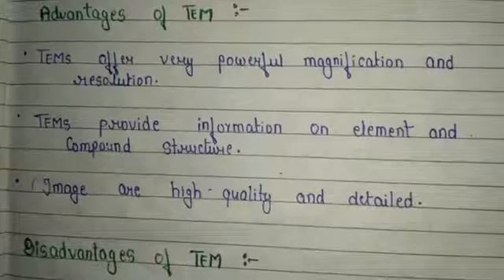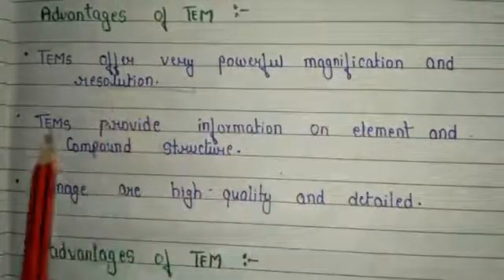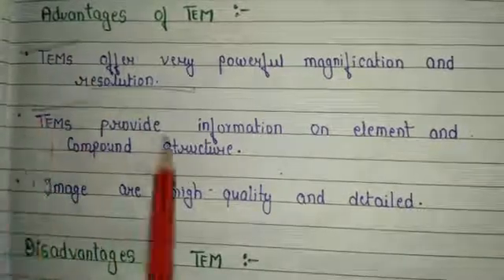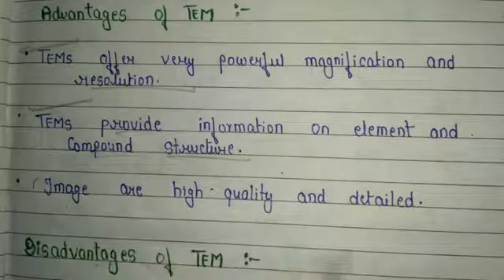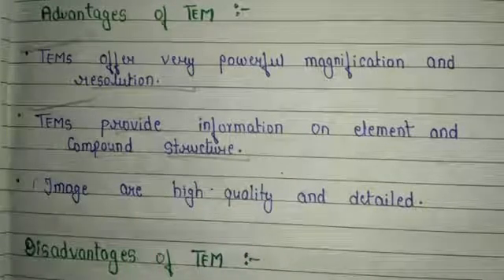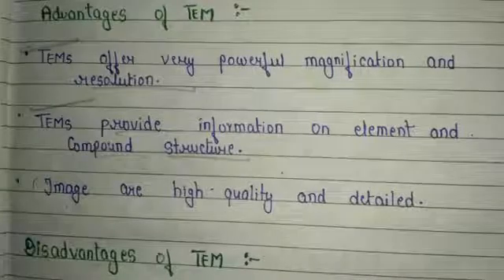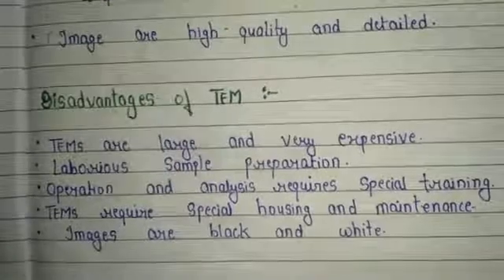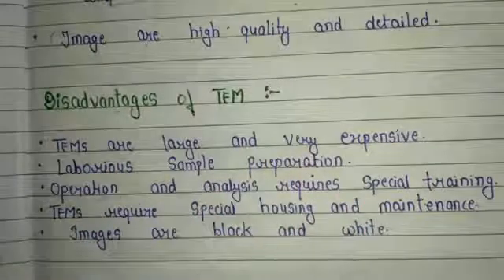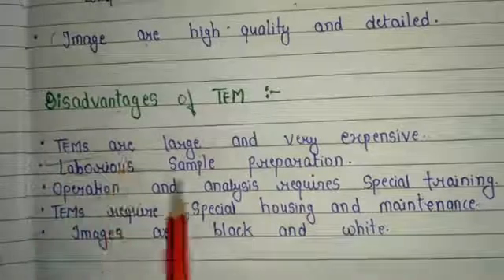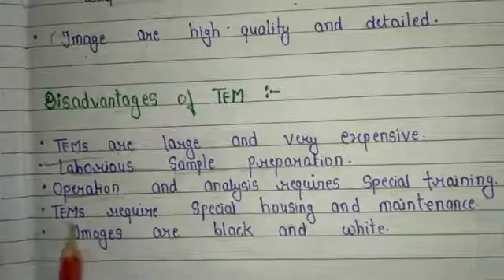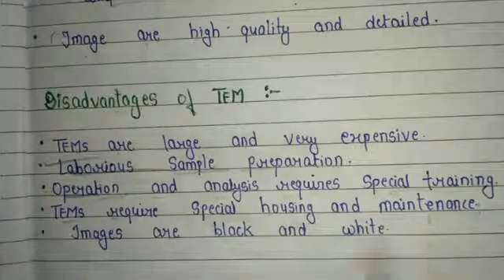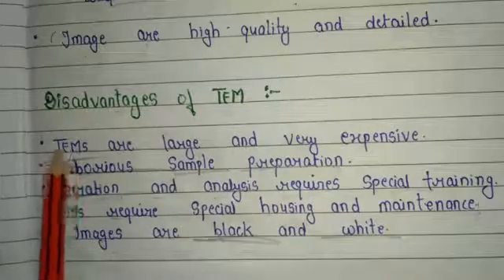Now the advantages of TEM. First, TEM offers very powerful magnification and resolution, and that is why we use TEM. Second, TEM provides information on element and compound structure, and images are high quality and detailed. However, there are disadvantages also. First, TEMs are large and very expensive. Second is difficult laboratory sample preparation. Third, operation and analysis require special training. Fourth, TEM requires special housing and maintenance, and images are black and white.